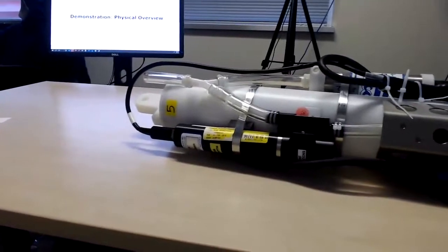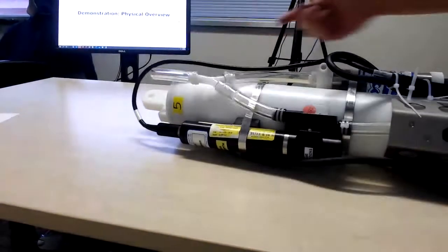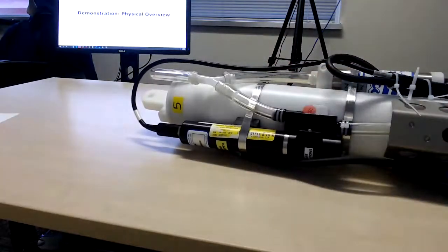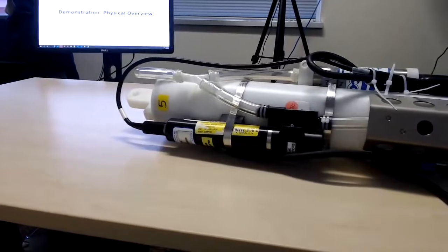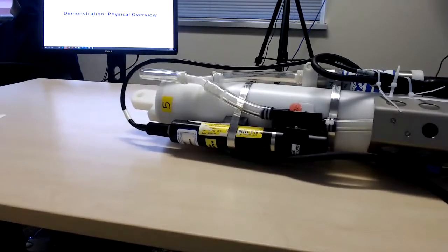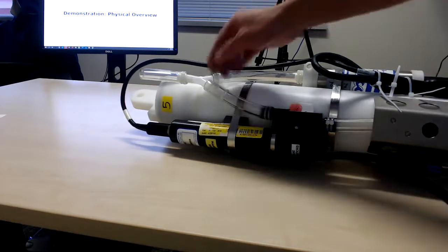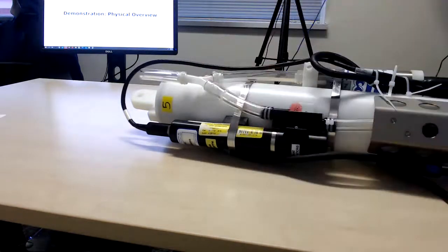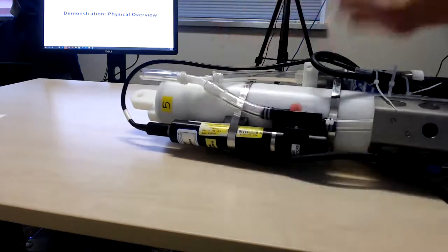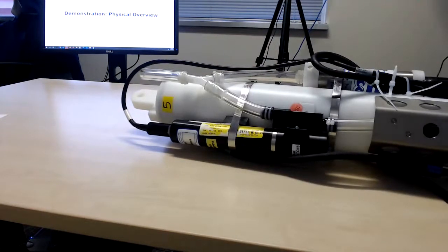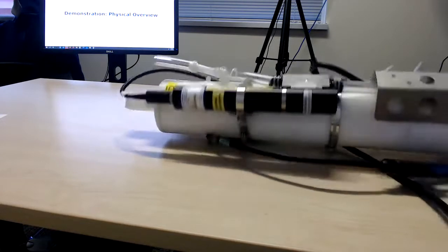What's important about that Y fitting is that this is a pathway for bubbles to escape from the plumbing. If you have bubbles trapped inside your plumbing, those are going to affect the samples that you get from your CTD, so removing those bubbles is really important. Bubbles want to float upwards, so it's important that the pathway for bubbles to escape is at the highest point in your plumbing. If you deploy this particular CTD in the horizontal orientation, you're not necessarily going to purge all the bubbles because this is not the highest point. This is the highest point. So you want to reconfigure your plumbing if you're deploying this in a horizontal orientation.